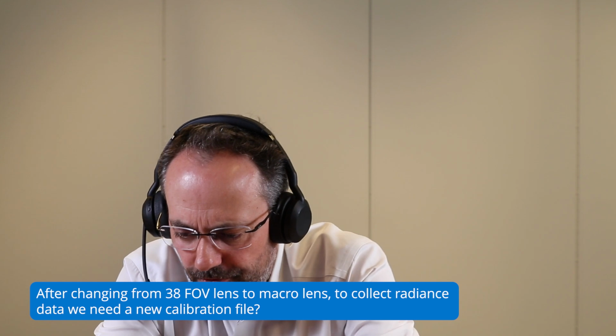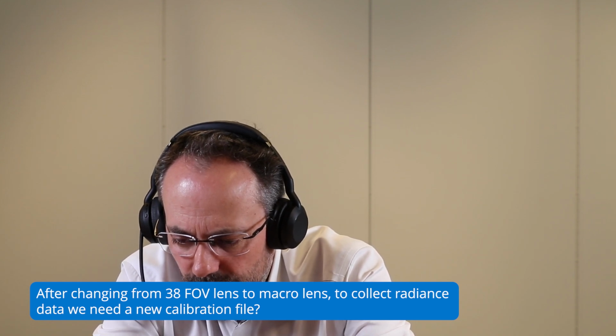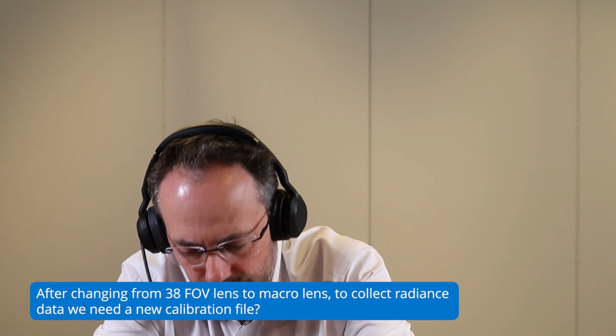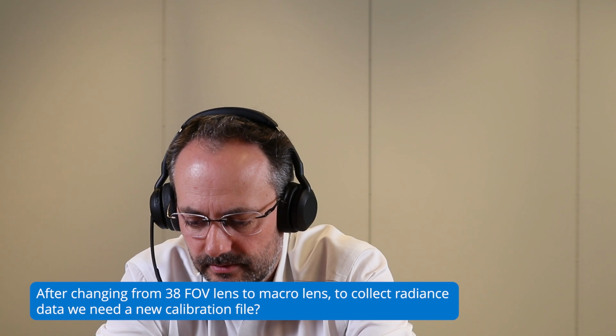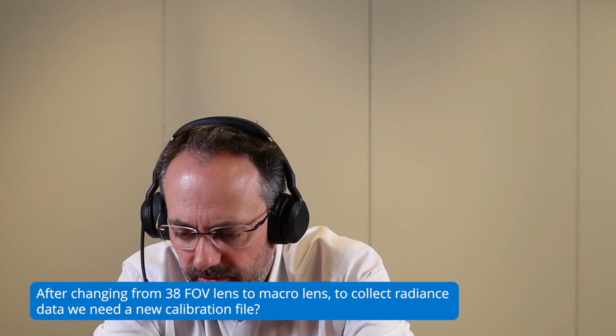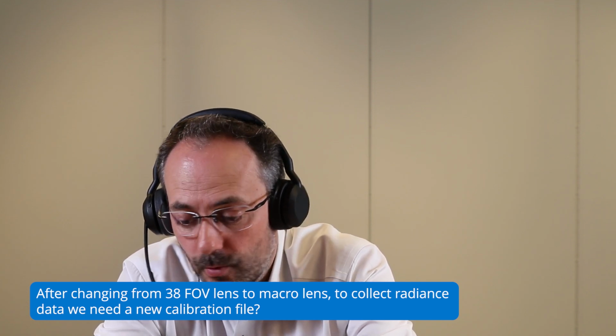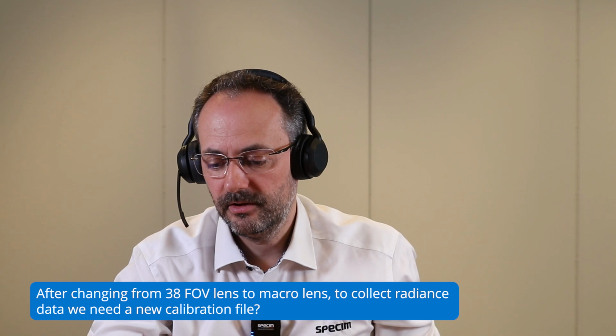After changing from the 38-degree lens to the macro lens, so we are talking here about an FX17, to collect radiance data, we need a new calibration file. Well, yes, because basically the radiometric calibration depends on the front objective that you are using, because it takes into account the transmission of the optic. So if you change a lens, you need to have a new radiometric calibration.